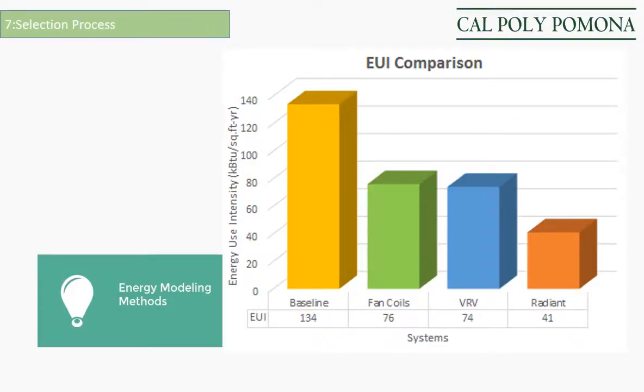Baseline has the highest energy usage intensity because it uses ASHRAE 90.1 minimum equipment efficiencies and energy recovery. Airflow is constant volume, so the fan is always flowing constantly, unlike the other systems, which use VFDs. All alternative systems use more efficient equipment. The radiant system has the lowest EUI because heating load can be satisfied without cooling or heating the air, unlike the hydronic fan coils and variable refrigerant volume indoor units.